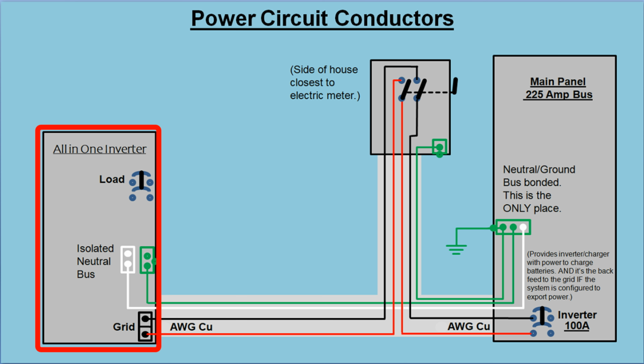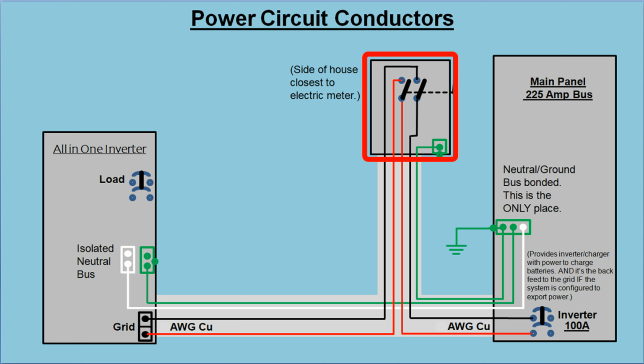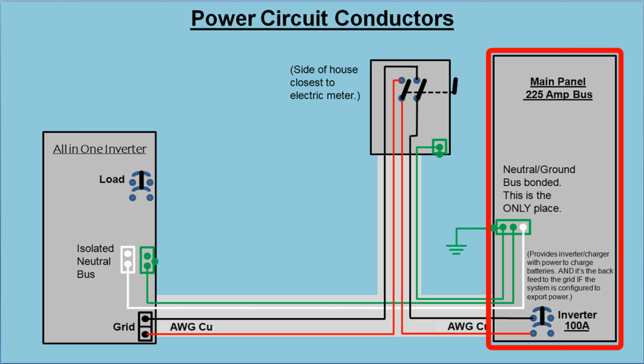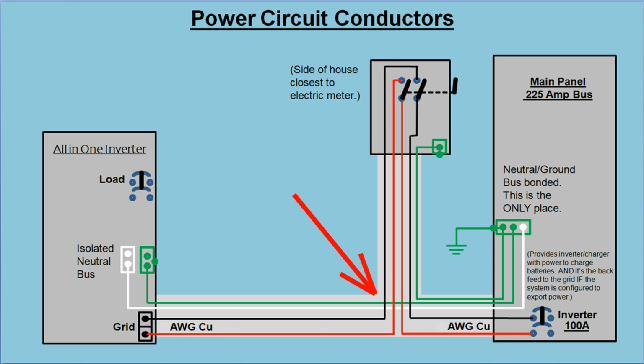Here's the all-in-one inverter. This is a disconnect to be mounted on the outside wall of the house, close to the electric meter. And here's the main service panel. This light gray upside down T represents a PVC conduit that houses the 240 volt AC 100 amp circuit conductors as shown. There's up to 100 amps of 240 volt AC passing between the grid terminals in the inverter and the inverter circuit breaker in the main service panel in the black, red, and white conductors as shown.